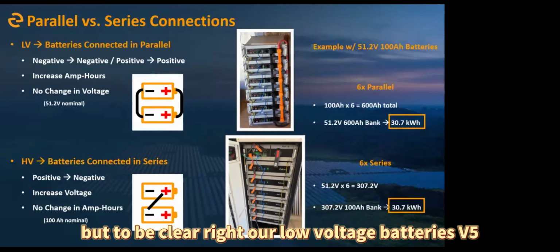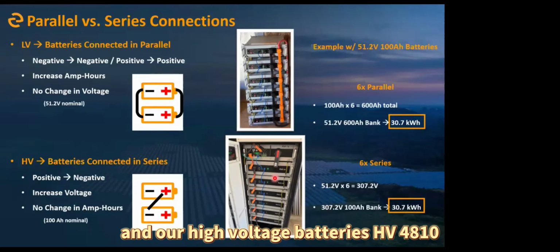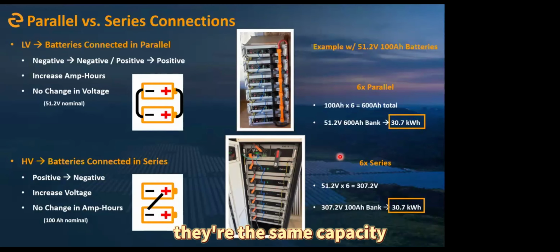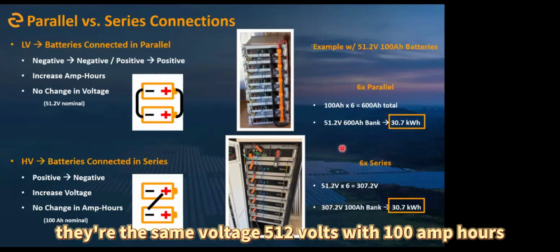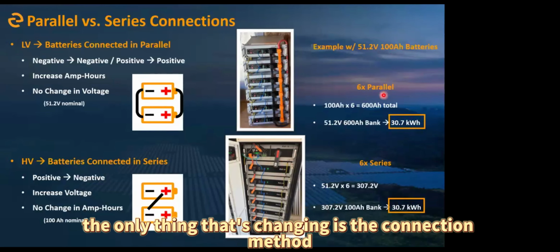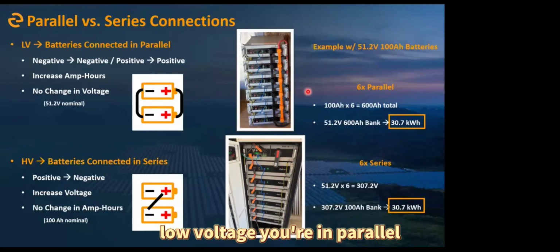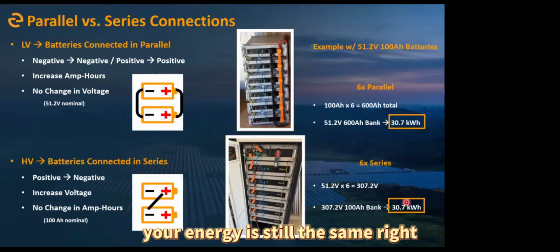To be clear, our low voltage battery V5 and our high voltage battery HV48100 are the same capacity, the same voltage, 51.2 volts with 100 amp hours. The only thing changing is the connection method - low voltage you're in parallel, high voltage you're in series. But at the end of the day, if your battery quantities are equal, your energy is still the same.